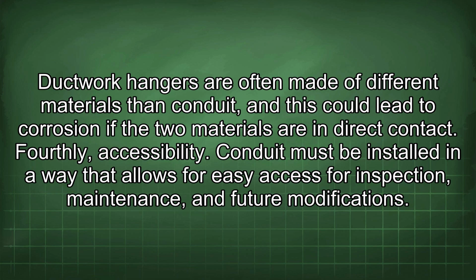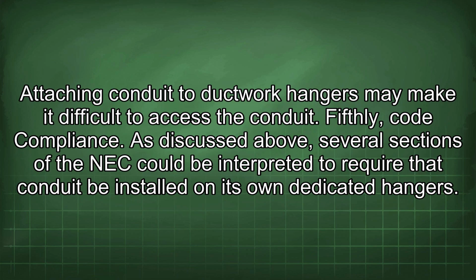Fourthly, accessibility. Conduit must be installed in a way that allows for easy access for inspection, maintenance, and future modifications. Attaching conduit to ductwork hangers may make it difficult to access the conduit. Fifthly, code compliance. As discussed above, several sections of the NEC could be interpreted to require that conduit be installed on its own dedicated hangers.